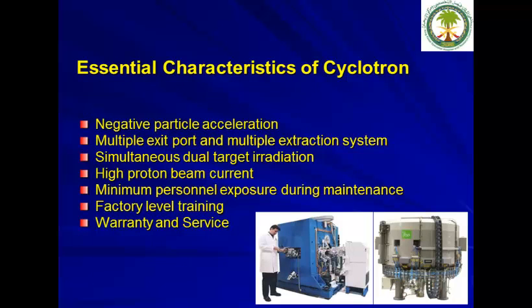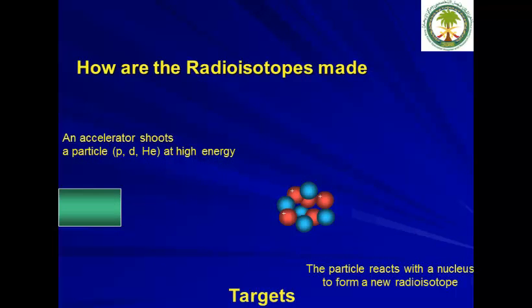When buying a cyclotron, essential characteristics include: negative particle acceleration, multiple exit ports and extraction systems, simultaneous dual target irradiation, high proton beam current for higher yield, and minimum personnel exposure during maintenance. You must also stress factory-level training for your staff. Pay careful attention to warranty and service terms, since spare parts and consumables may be excluded — be very careful about these details.